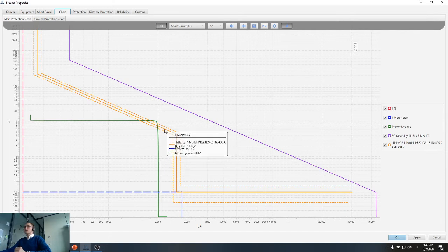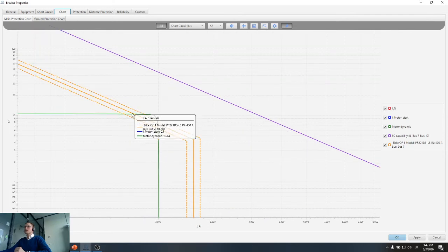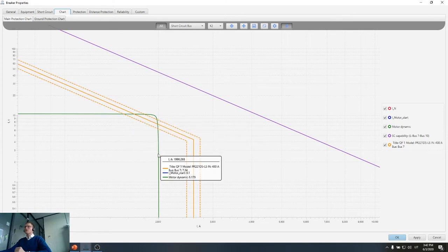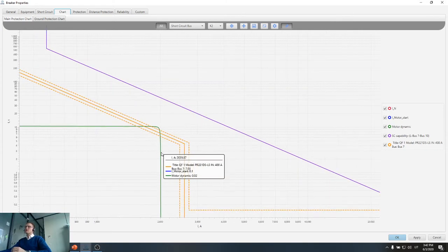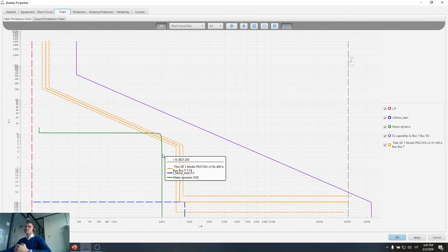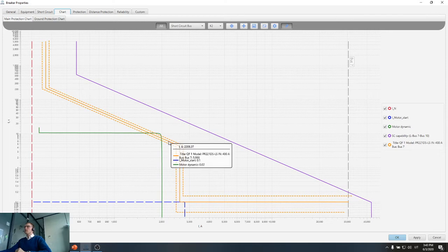We can see that when I reduce the time setting, my protection device in this area here has cross-section points with the motor starting curve, which means that during motor starting it is possible that my protection device will trip, which is of course not good, because motor starting should be allowed.